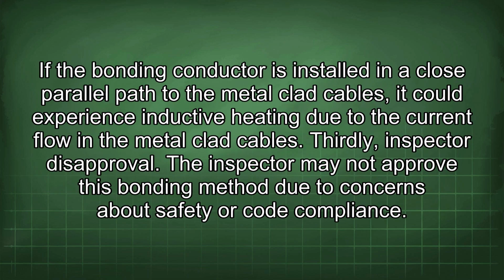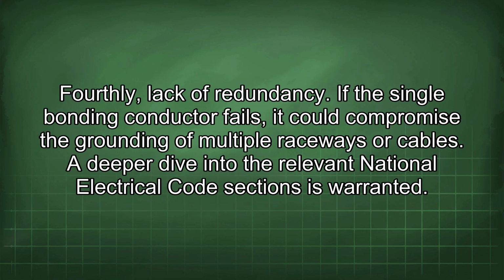If the bonding conductor is installed in a close parallel path to the metal-clad cables, it could experience inductive heating due to the current flow in the metal-clad cables. Thirdly, inspector disapproval. The inspector may not approve this bonding method due to concerns about safety or code compliance. Fourthly, lack of redundancy. If the single bonding conductor fails, it could compromise the grounding of multiple raceways or cables.